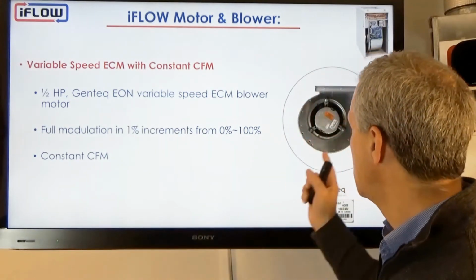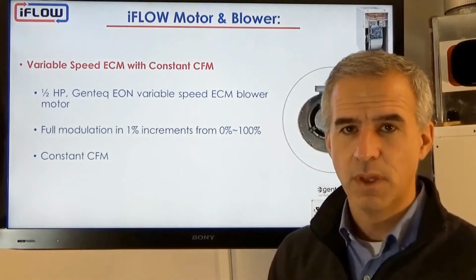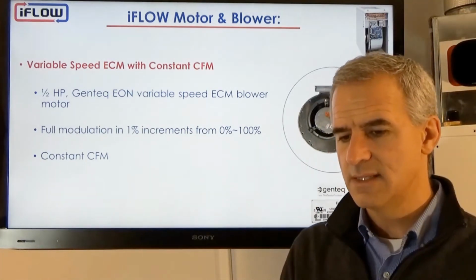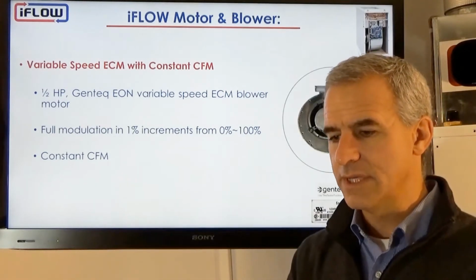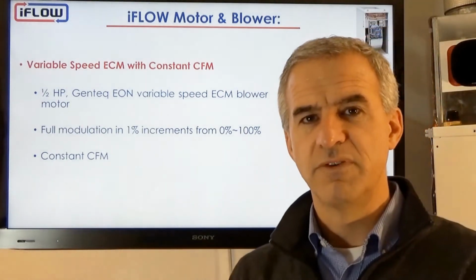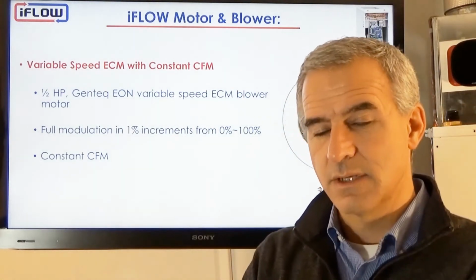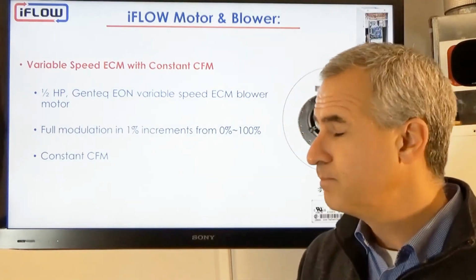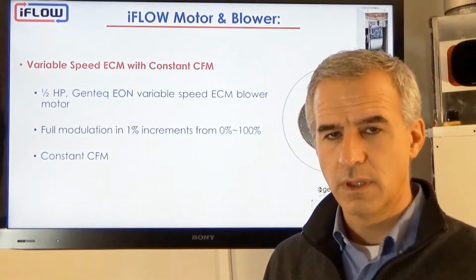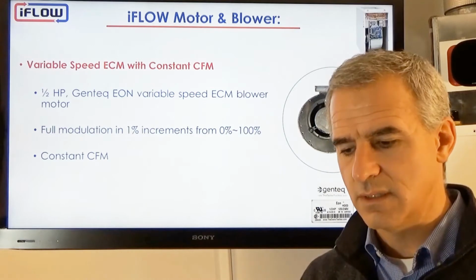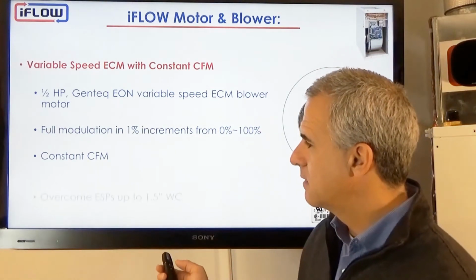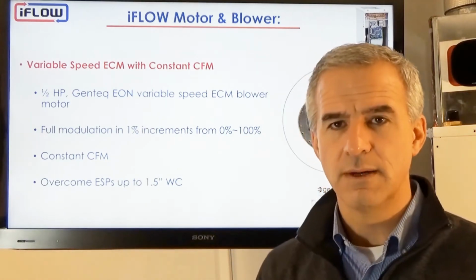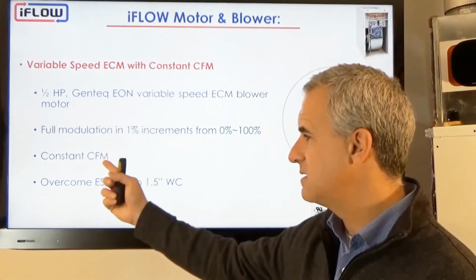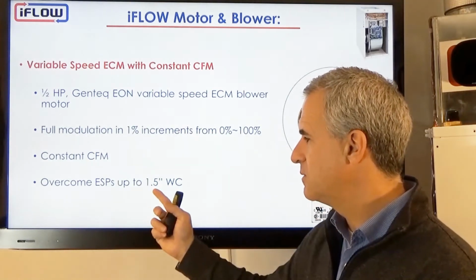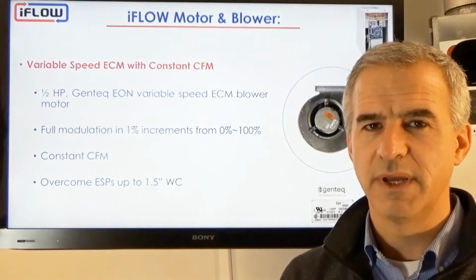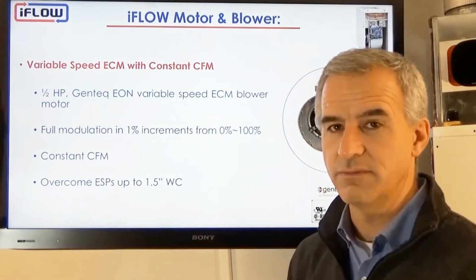The constant CFM basically looks at maintaining the CFM regardless of the external static pressure. So as the pressure in the ducting system increases, for example over time perhaps your filter gets more clogged, that's going to act as more of a restriction against the air moving through it. In that case, the motor will automatically increase the power to the blower motor to overcome the increased pressure and maintain the CFM. So even with a static pressure of up to 1.5 inch water column, we can still maintain the CFMs we need to deliver all of the heating and cooling.